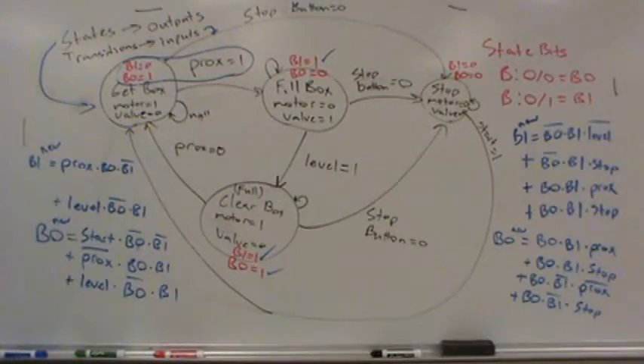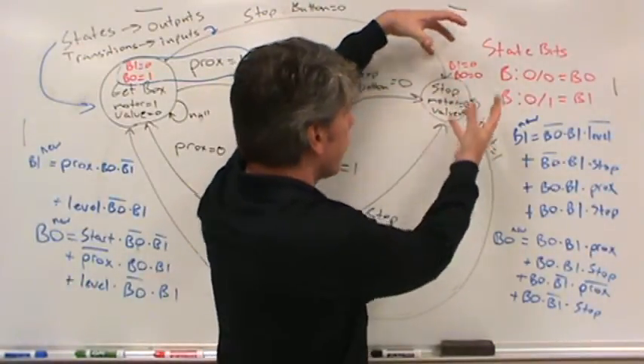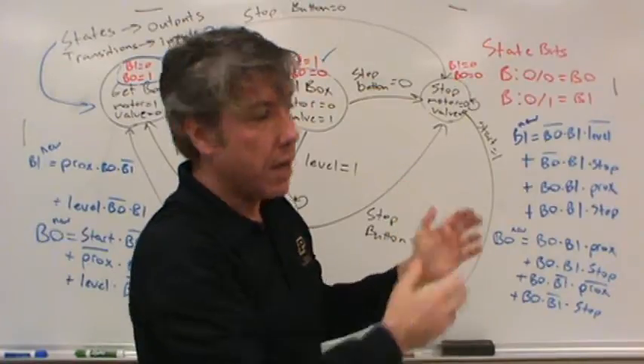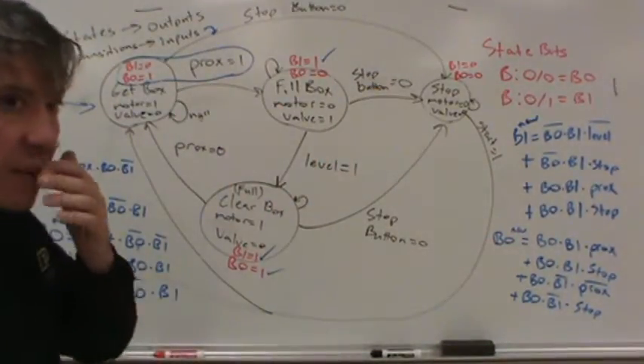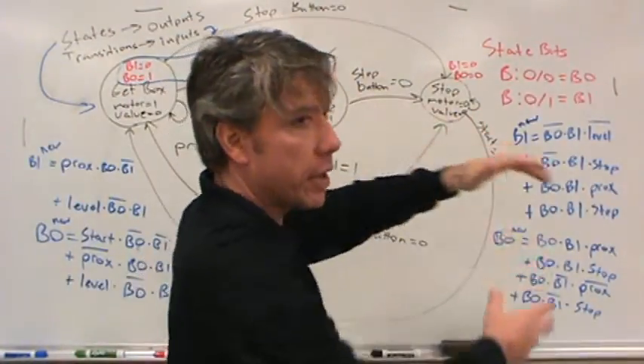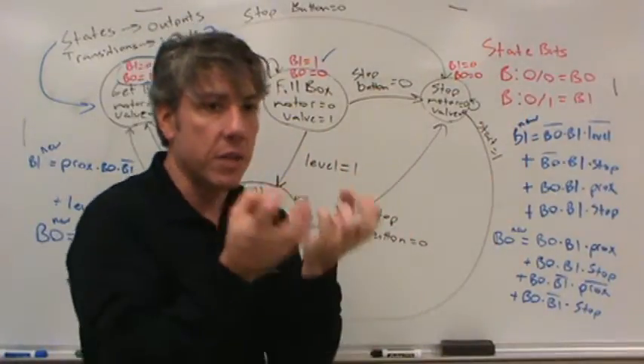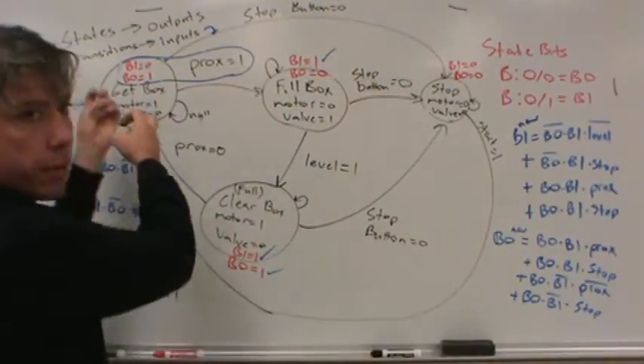I think you guys got it. Good job. So, stop. You got it. Now, there's a bug. There's already a bug. You know where the bug is? Let me show you something. Do you notice that the value of this bit is going to be affected by this rung? The value of which bit? The value of bit zero is going to be affected by rung zero. Right. Then the PLC is going to move on to rung one and try to calculate bit one based on bit zero. It's already been changed. My point here is that bit zero and bit one are not independent entities. They're one thing together that represent the state that you're in.